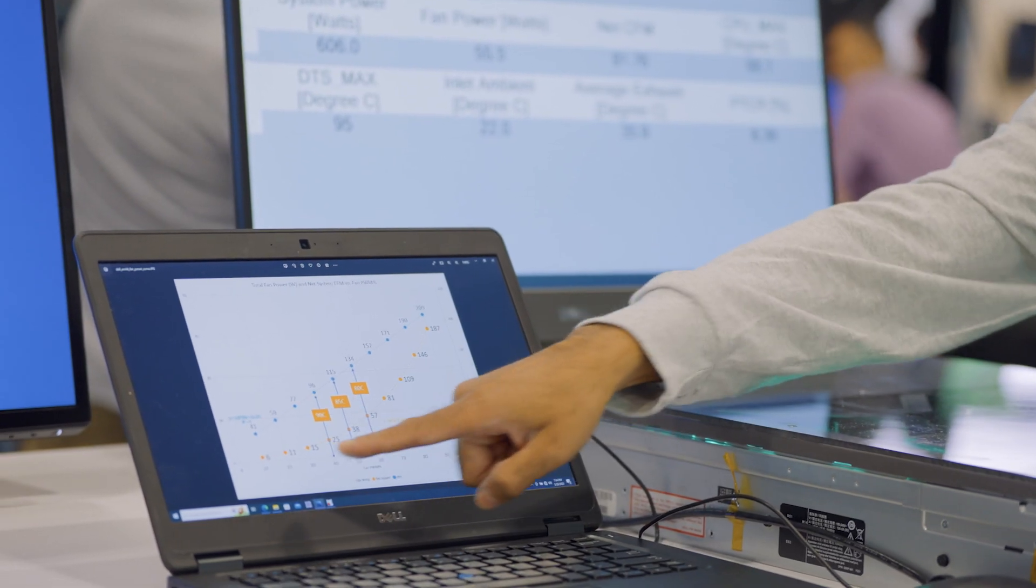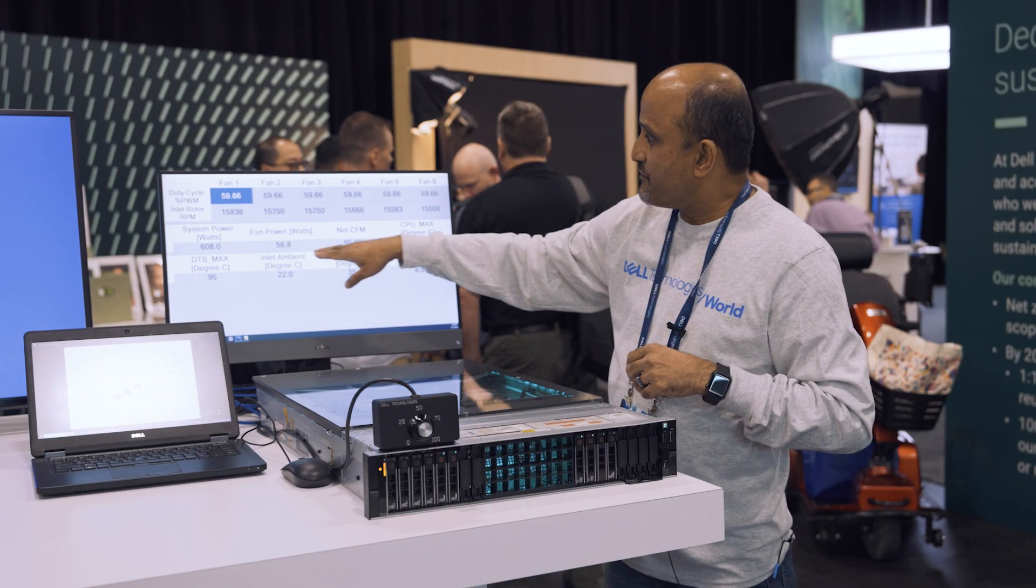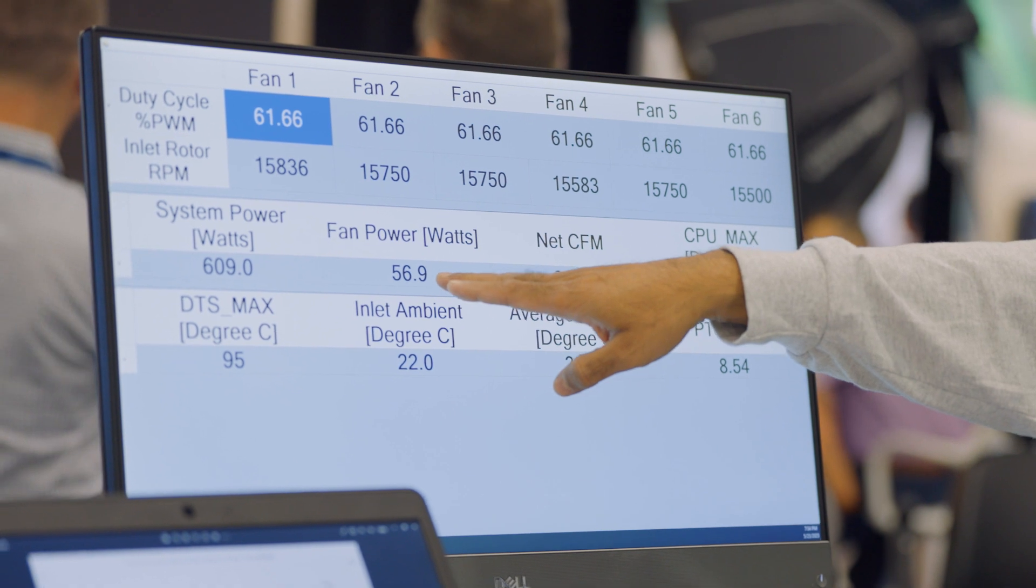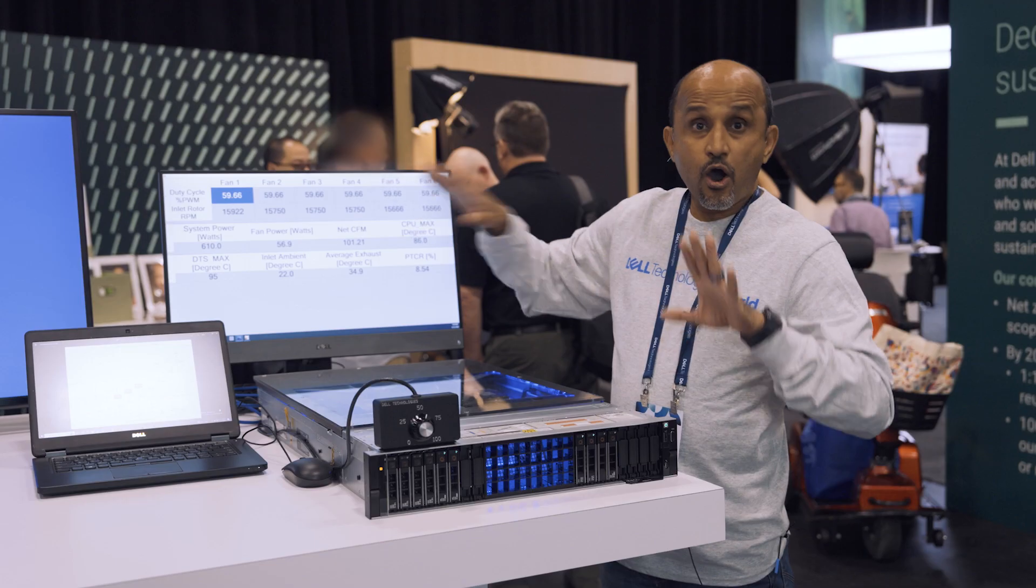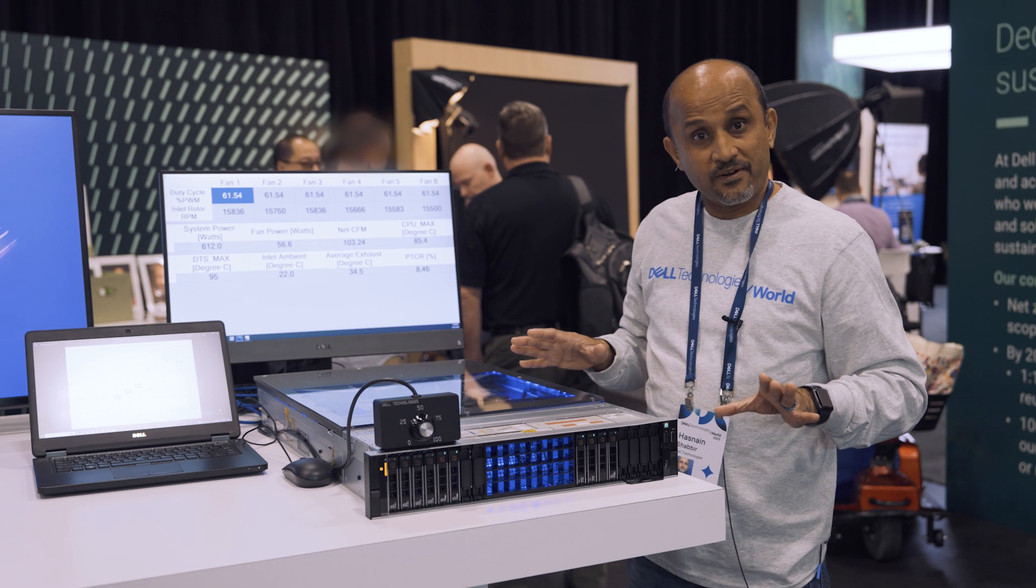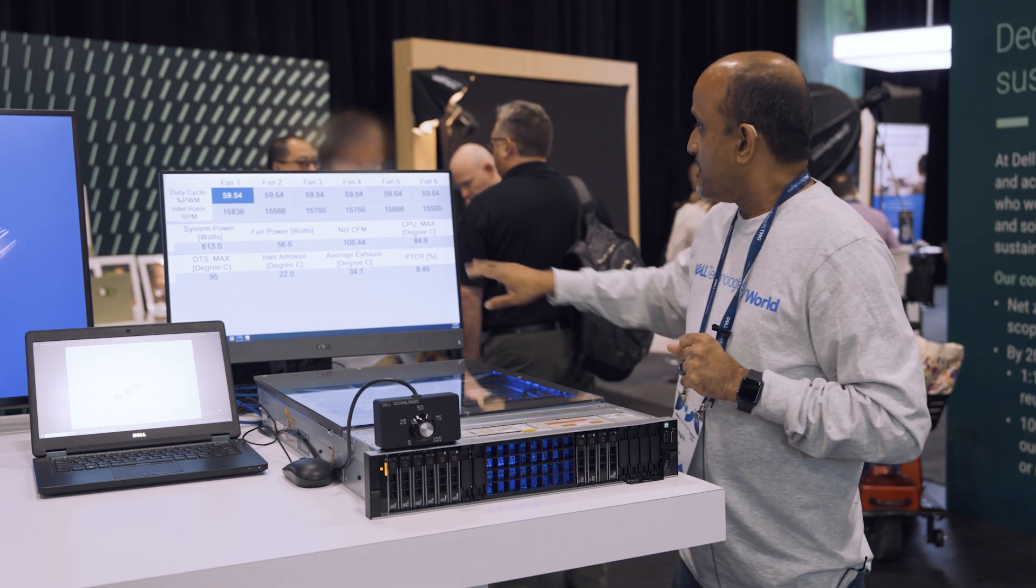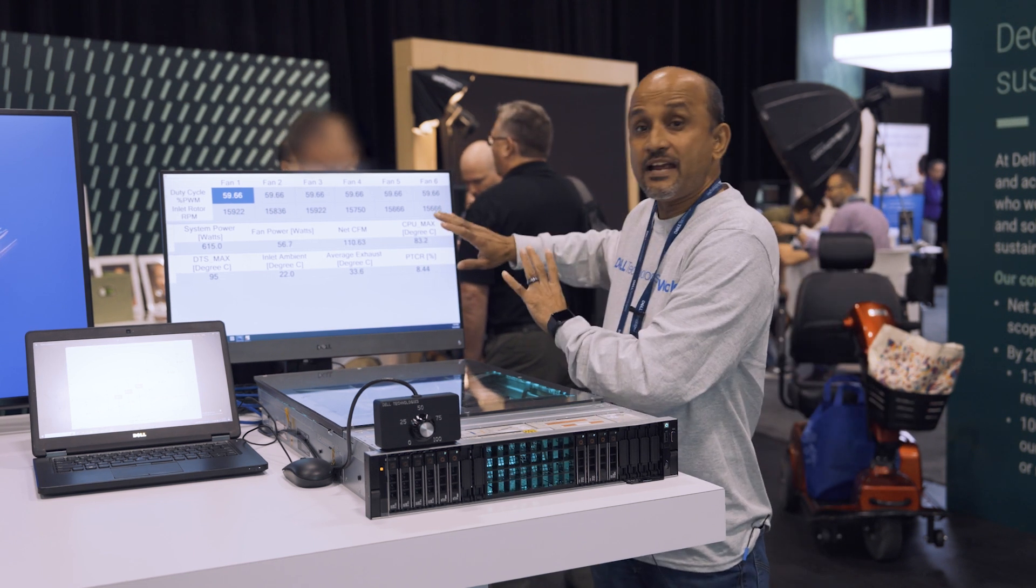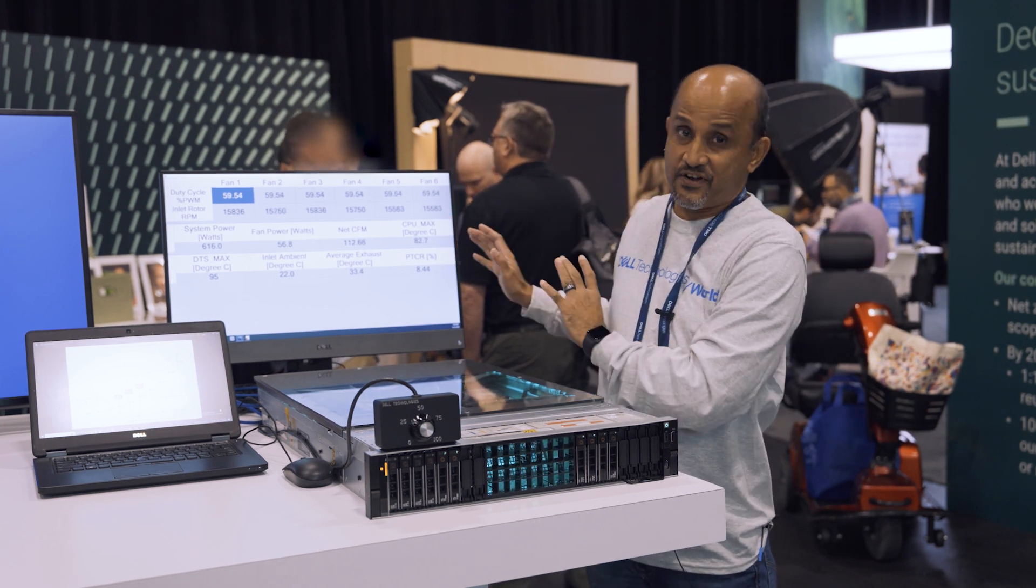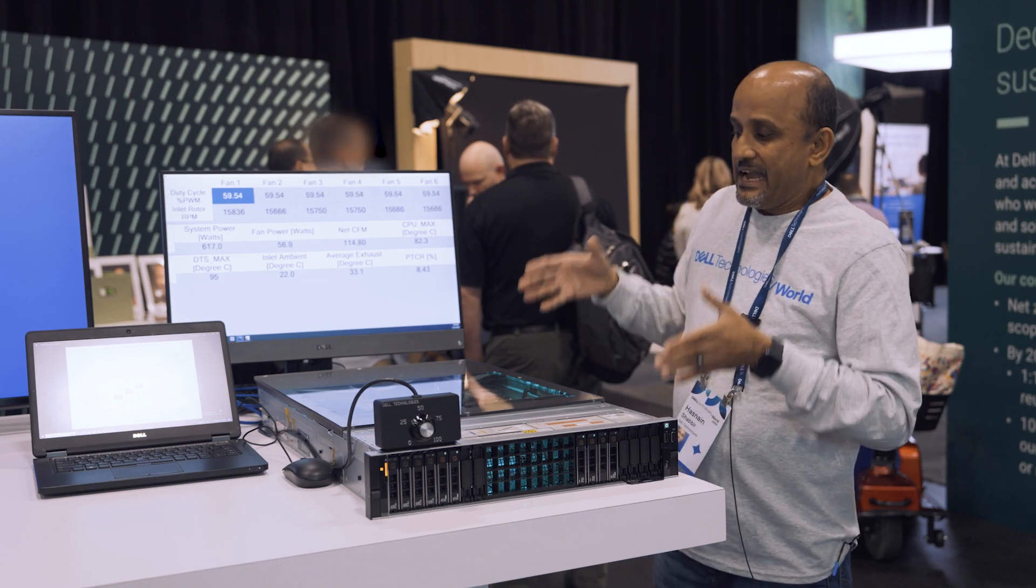Not many people understand the curve and what impact it has on their system. Here you can see we were operating at 13 watts, we are already four times that power. All that power is waste power. You're not going to get anything out of it. CPU is being over cooled, but nothing from a performance perspective benefits you.